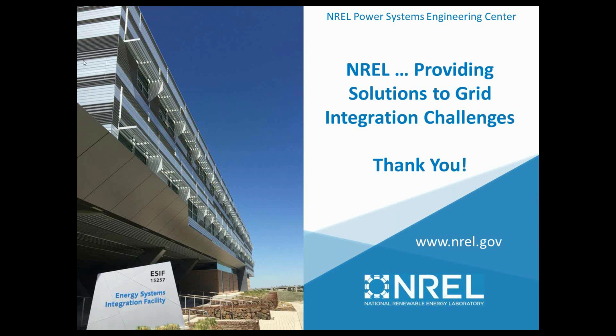Typically, these devices are set to run at or close to a fixed power factor, whether it's unity power factor or 0.9 power factor, lag or lead, so it depends really on what those DR settings are. If it's allowed to move those around and provide reactive power, then that's probably going to be the thing that either allows it to potentially support or not support an island. Now, if it's fixed within a very tight range, then you probably will never be able to support the island because you'll never have enough reactive power inside there. But again, it depends on what kind of loads are in the system and may require additional evaluations.